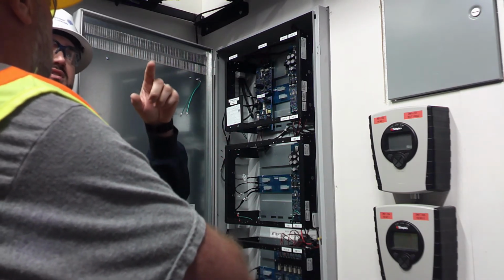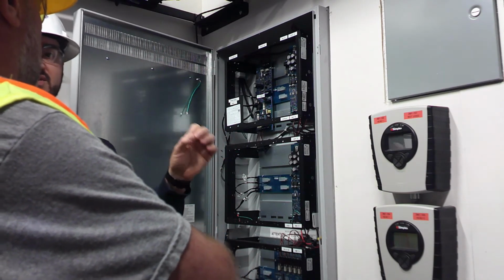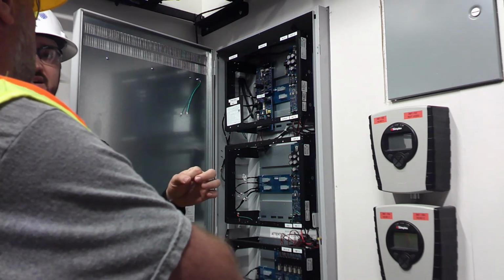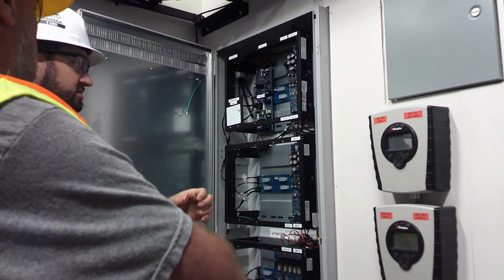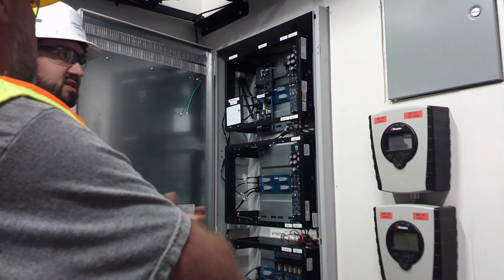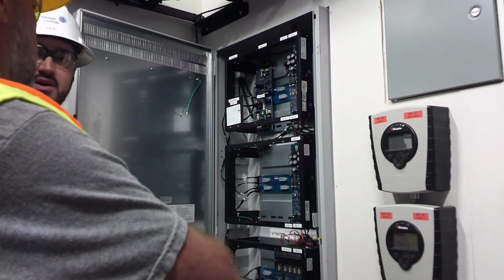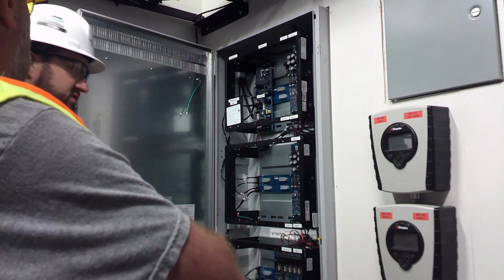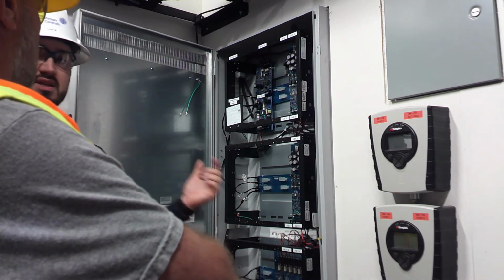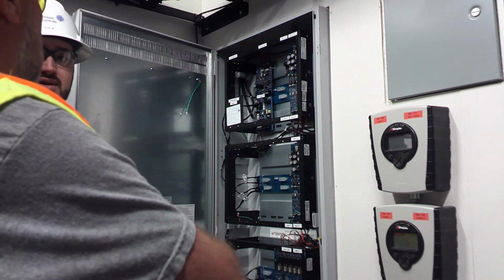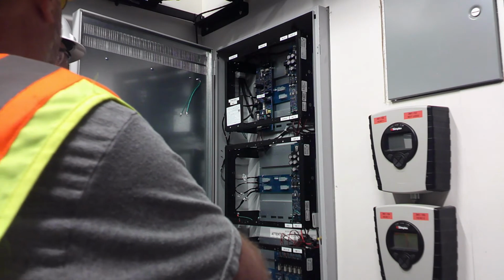Like a smoke detector, you just have to walk around and physically see that it has a solid light instead of a heartbeat. But it will act as a standalone. If something happens in this sector, it will still trip an alarm, it just won't tell the main panel what's going on, and it won't dial out on the phone lines.